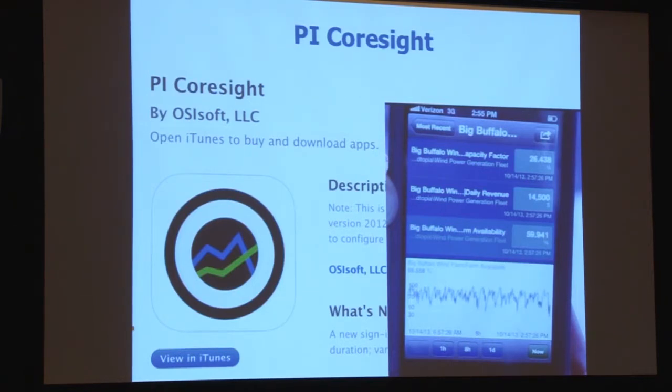It's monitoring only. And the real trick in doing this sort of thing is creating these displays. So just like you had to create displays for your SCADA or DCS, you'll need to decide what kind of displays you want on your mobile devices. They probably will be a different format because they're going to be a smaller screen. You may not want to provide all the data because there is a cost to pushing the data out. You have to build the displays, and you probably have to buy what's called tags or points from the vendor.